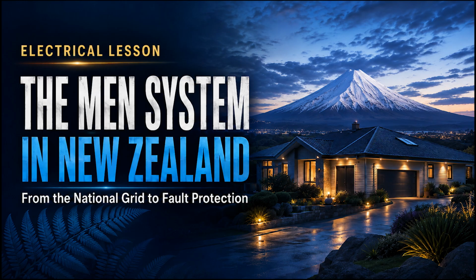Now follow one socket outlet circuit. The active passes through its protective device, the neutral returns to the neutral bar, the protective earth returns to the earth bar. At the socket outlet, the active and neutral deliver power to the appliance. The protective earth connects the accessible metal case to the fault path. If the appliance is healthy, current goes out on active and back on neutral.